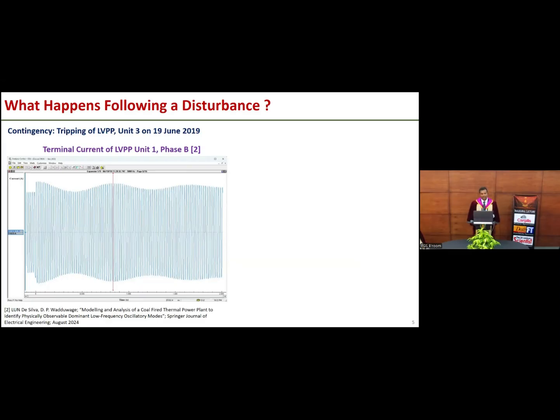What we see is the generator speed accelerates and decelerates. So how does it appear in actual system variables? Now, in this case, what I am showing here is the stator current variation of the Lakvijay power plant unit 1 subsequent to a failure in unit 3. So you can clearly see that in steady state, the current is varying at the 50 Hertz component, or at the fundamental frequency, it's a sinusoidal waveform. And that sinusoidal waveform itself has a magnitude and a phase angle.